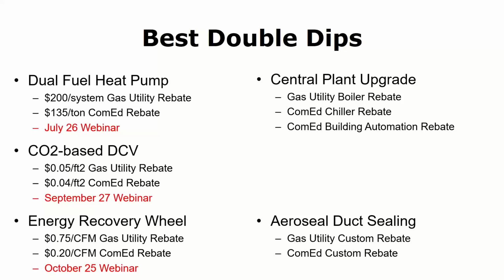Some of these projects - man, we did one at a hotel, I think a Hilton downtown Chicago, with a 60,000 CFM air handler, big and huge. The reduction was 12,000 CFM of duct leakage, and that wasn't even on a rebate - that was before the rebates existed for this, or rather, the rebates existed but no one knew how to apply them to duct sealing. They did it and made the money back without even having the rebate. You can get a lot of money from both the gas and electric side for doing large duct sealing projects like that.